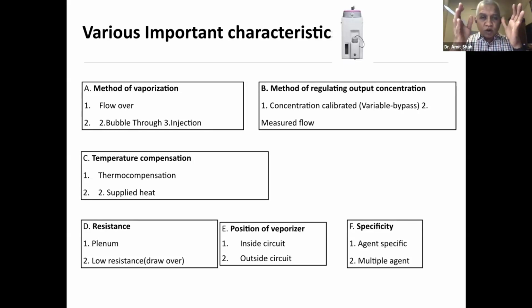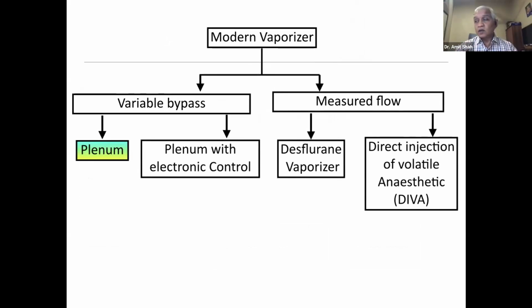Okay. On the basis of the technique of vaporization, regulating the output, temperature compensation, resistance, position of the vaporizer, and specificity, we can identify and classify the modern vaporizer. Modern vaporizers are mainly two. One is variable bypass, and in the other system, a measured flow passes through the vaporizer. Variable bypass can be a plenum vaporizer, or a plenum vaporizer with electronic control. The desflurane vaporizer is not a true variable bypass; basically it is a measured flow which is added to the circuit. So the desflurane vaporizer and DIVA are measured-flow types of vaporizer.